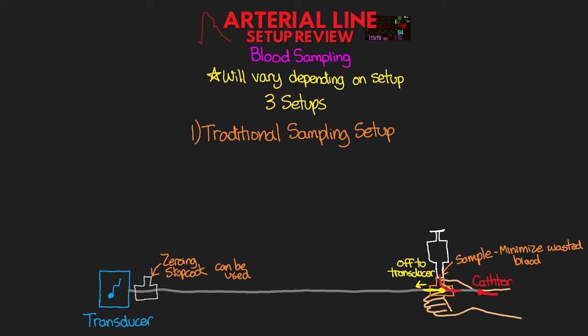This will have an open line from the open port to the catheter. From here, you would withdraw your waste and then turn it off to the patient. You'd then disconnect your waste and then attach your syringe for the sample, and then turn the stopcock back off to the transducer, and this will allow you to draw your sample. Once you have your sample and you're done, go ahead and recap it at this point, and then turn it off to the open port, and then use the flush wand to flush any remaining blood in the line back to the patient. So while this traditional setup does work, it does pose some potential risks.